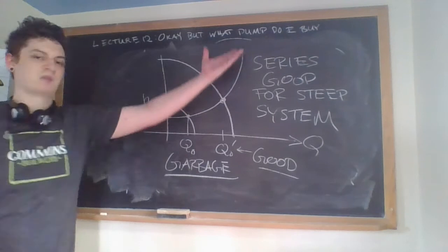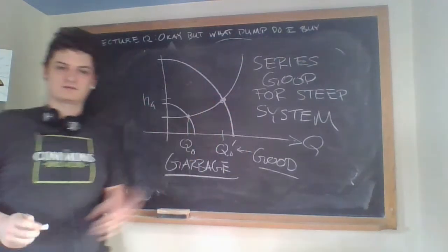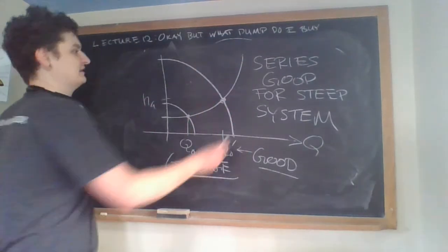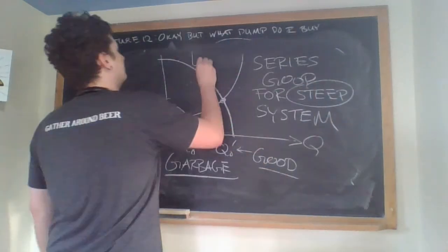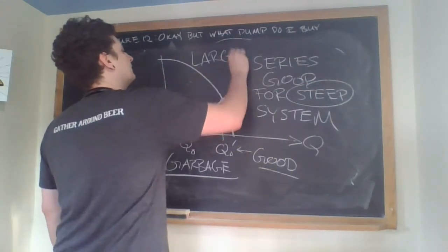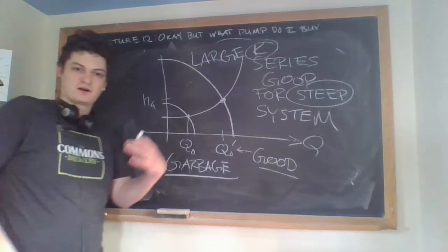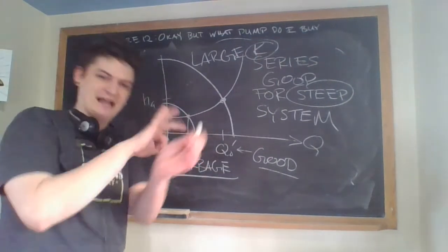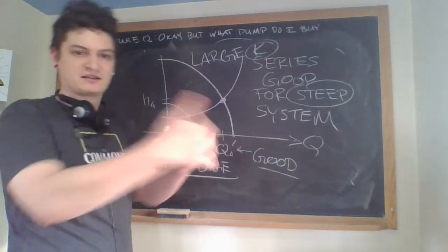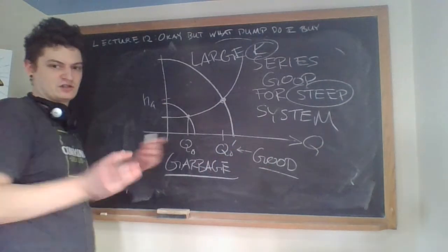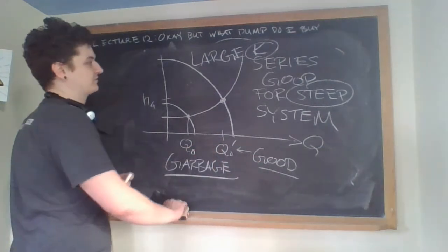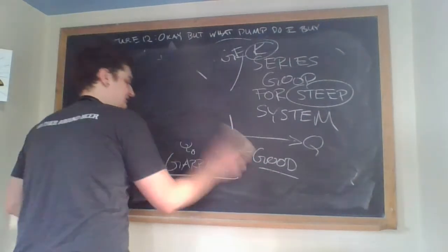Right? So series pumps are good for steep system curves. Steep system curves, right? What does steep mean? Large resistance values in your pipe. So those are fuel systems, right? Systems with very tiny pipes, intricate turns, lots of minors and Ks, and a very tumultuous path that the fluid has to go through. You're going to get very steep systems.